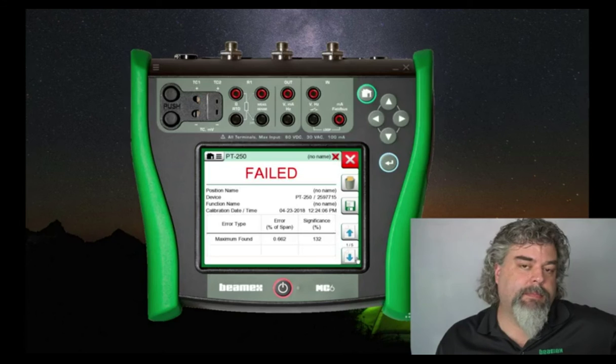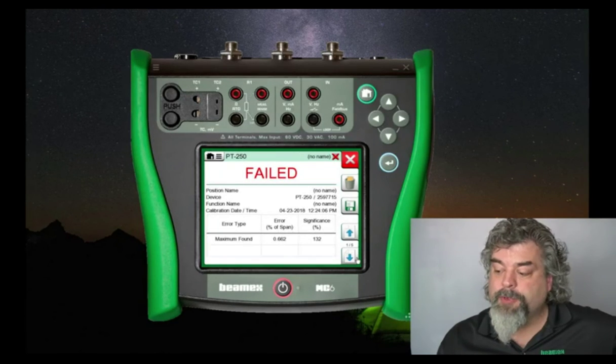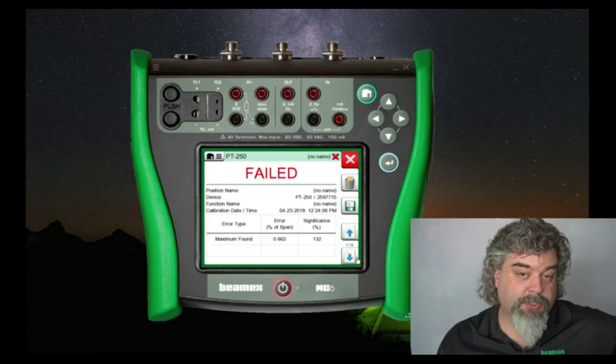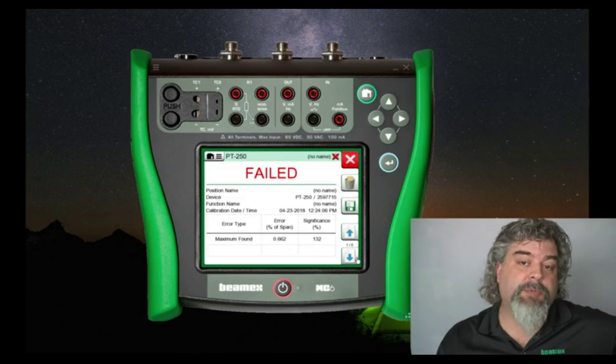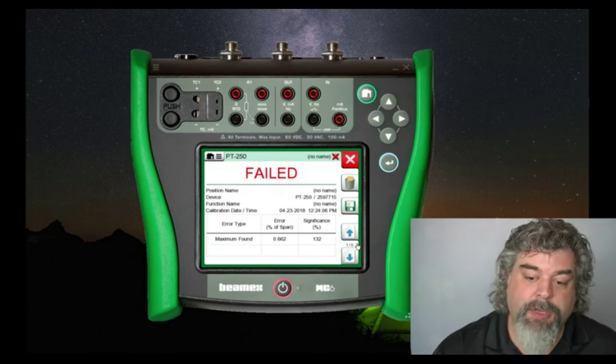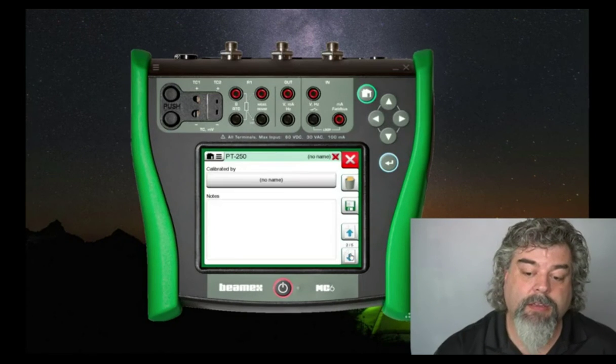So this means I'm not a good calibration technician. No, that's not what that means. This means that the device itself failed. As long as all of your connections are set up and they're good, this is the transmitter that failed and not you as a technician. All right? So from here, let me move this out of the way.